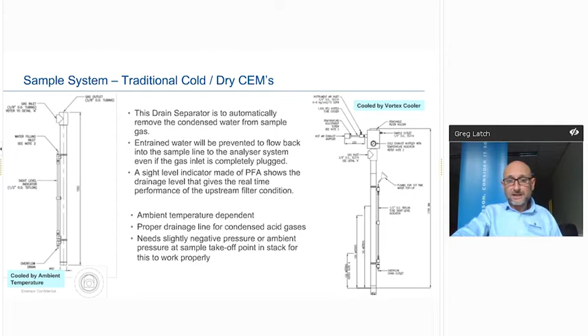So the goal is moisture removal, obviously, in a cold dry aspect, moisture removal prior to the sample gas transport to the analyzers, and or therefore some management of dryers just before the analysis. If you don't have that, then you will have, dare I say, maintenance issues ongoing with your analysis system, and more to the point, dare I say, some potential large bills on your gas analyzers themselves. They don't like liquids going through them. Okay, I think I've covered a quick mention too, these sort of styles of systems though aren't always very suitable for DeNOx. As I say, in this particular case too, I just had a note for myself that Nafion dryers, for example, don't work very well with ammonia, unfortunately. So it's one of the challenges in that space.